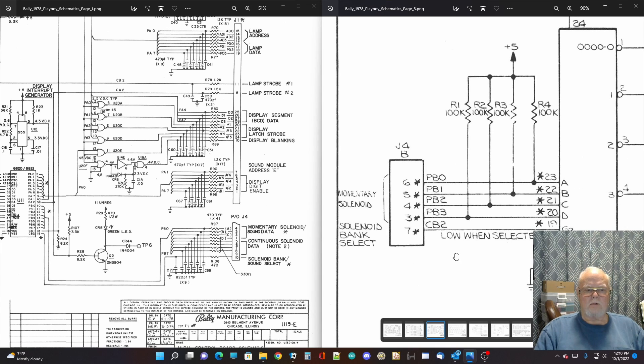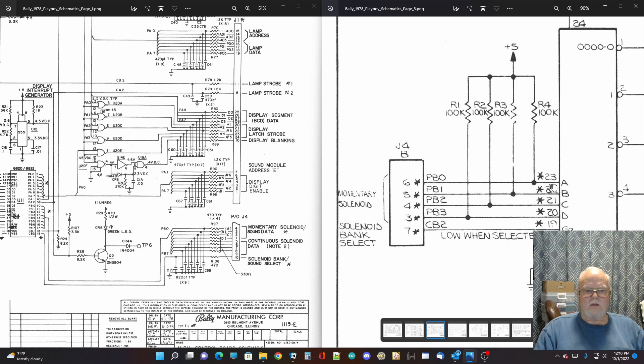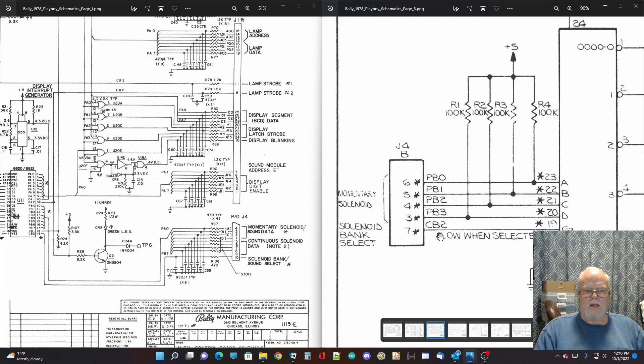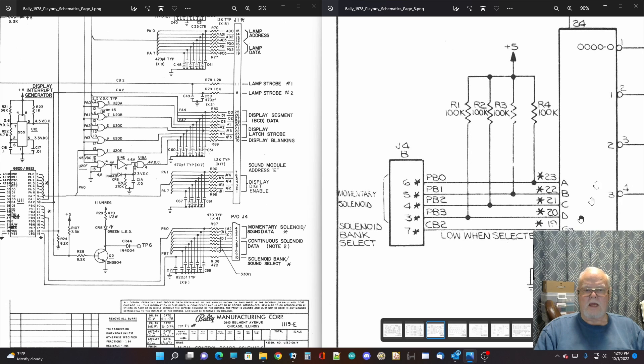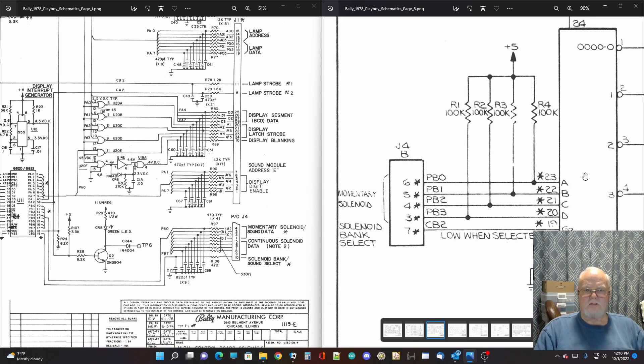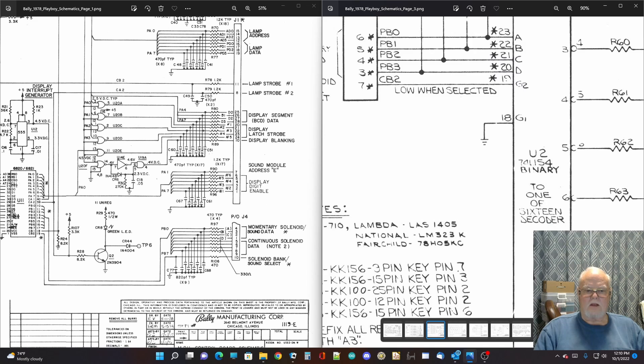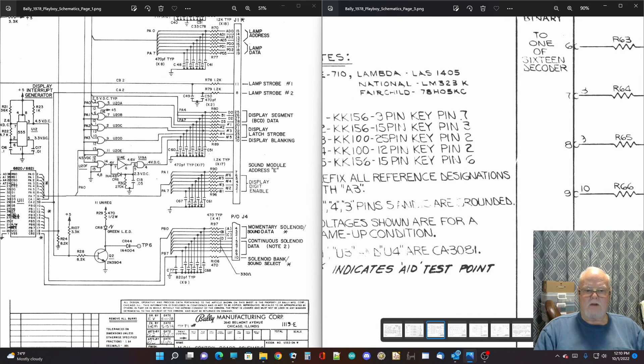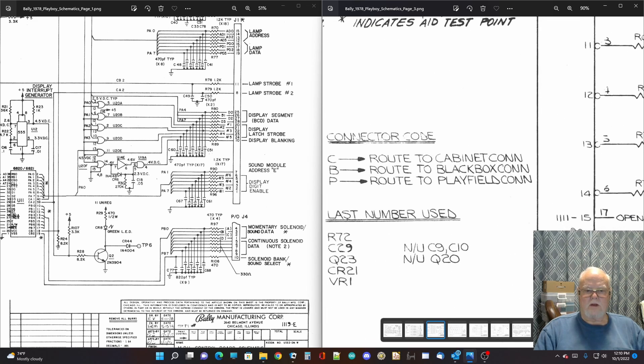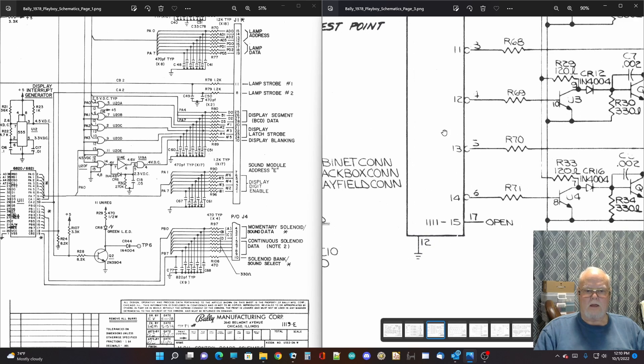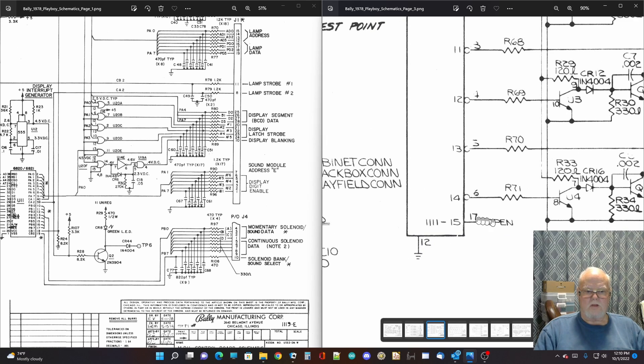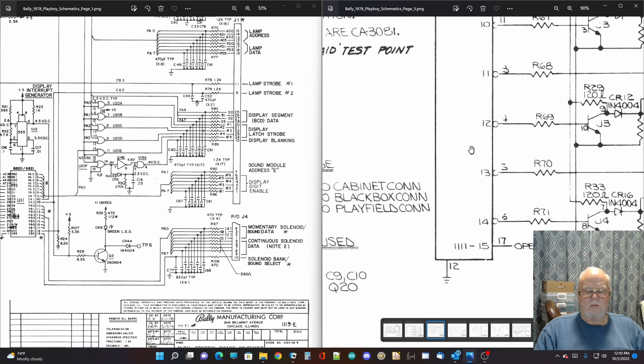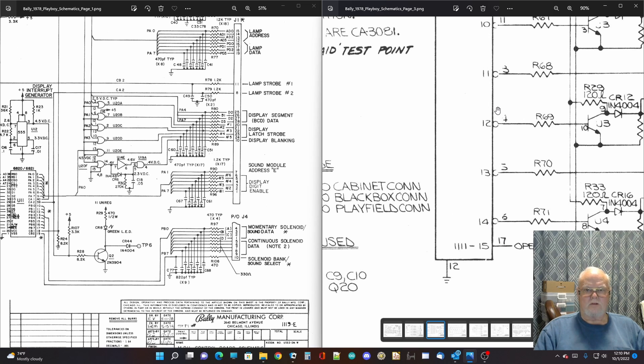So now the screen on the right hand side is showing the solenoid driver board. And if you look here, the same four A, B, C, and D come into this solenoid selector and the solenoid bank select line comes into the gate on this four line to 16 line decoder. And one of the key things that you need to understand is that the very last number 15, which would be all lines high is not used. It is left open.